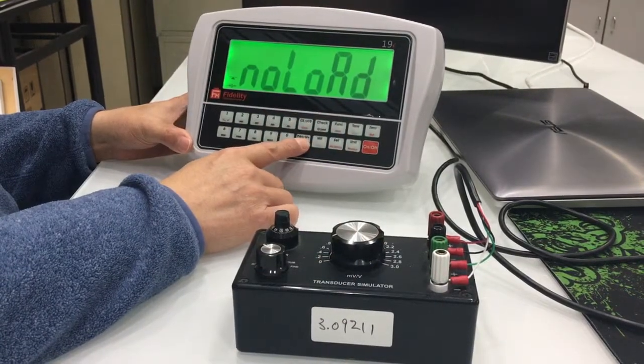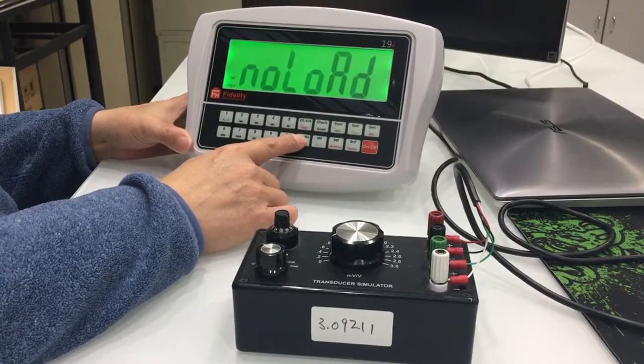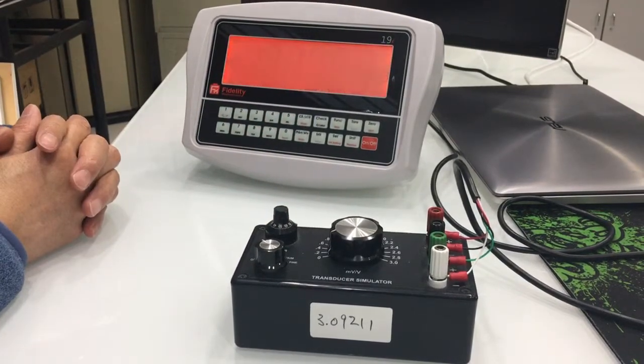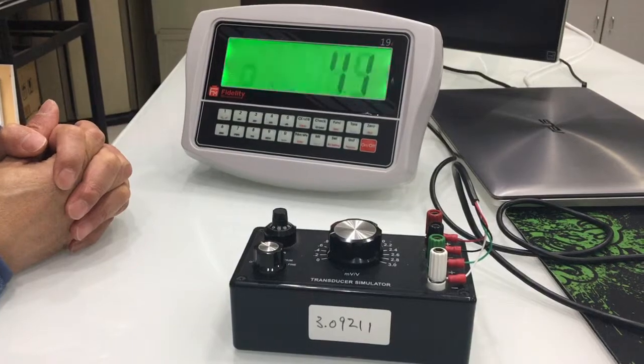Then the indicator is now ready for zero calibration. I'll remove all the load from the load cell and then press enter. The zero calibration procedure is now completed.